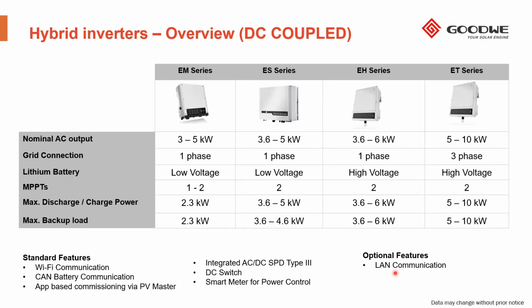There is a question regarding Wi-Fi. Wi-Fi is standard, so the Wi-Fi module is supplied in the box. If you need LAN, so if the inverter is too far from the customer's router and the Wi-Fi signal is not strong enough to create a stable connection, then you have the option of replacing the Wi-Fi with a LAN module to connect essentially an Ethernet cable between the inverter and the customer's router. I understand that installers or electricians prefer hardwire cables, so we do have that option there.